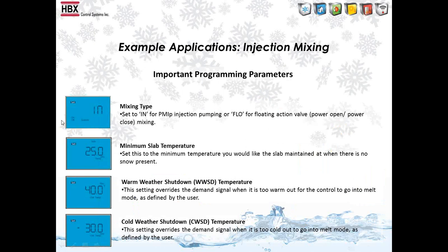So for that application, for setting it up, you need to make sure that you set your mixing type to IN. So there's FLO or IN. So you need to set it to IN, which means it's injection. That is the default setting for the control. So if you're using it for floating action, then you would actually change that. Otherwise, that is the default.